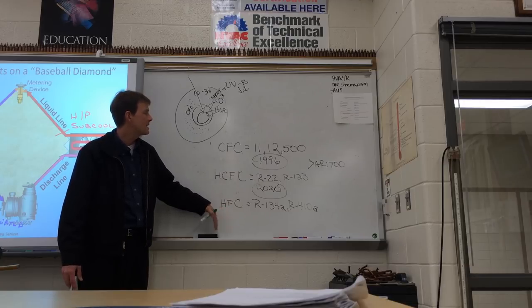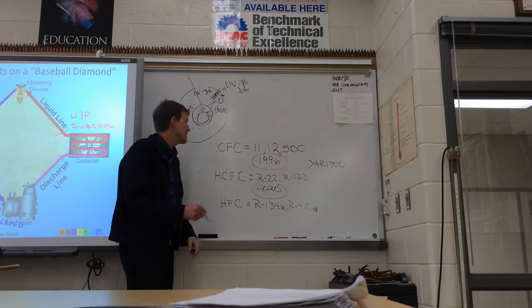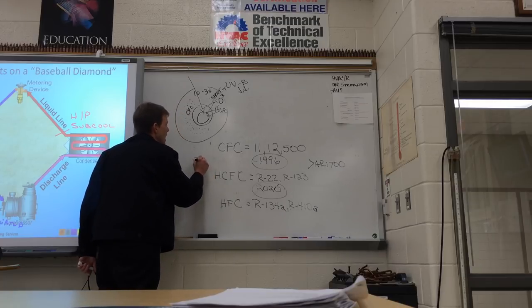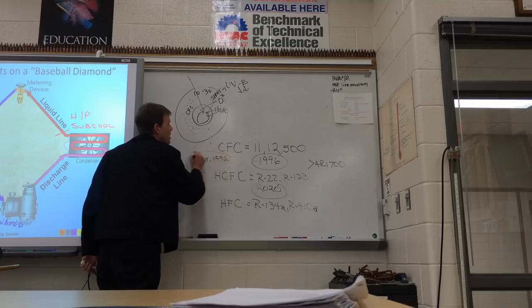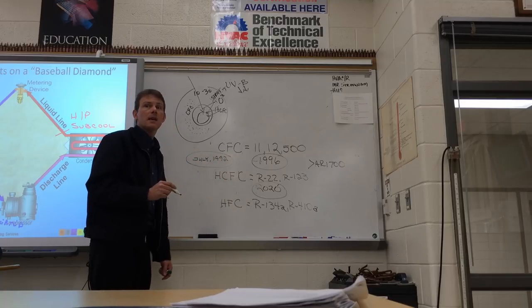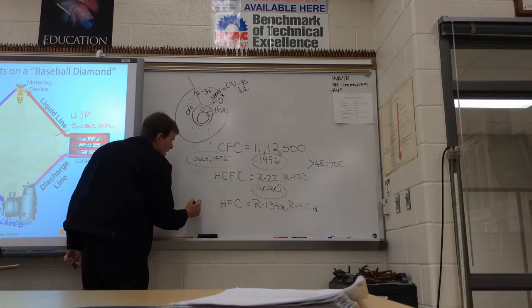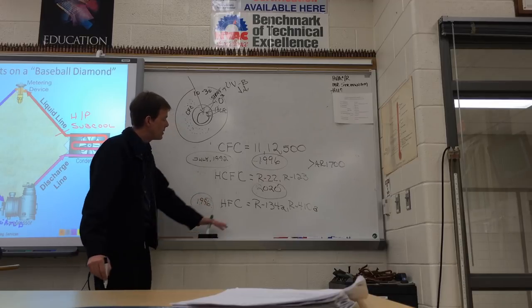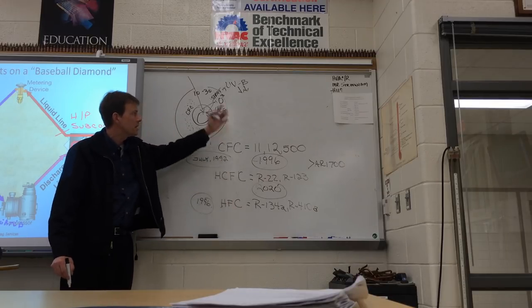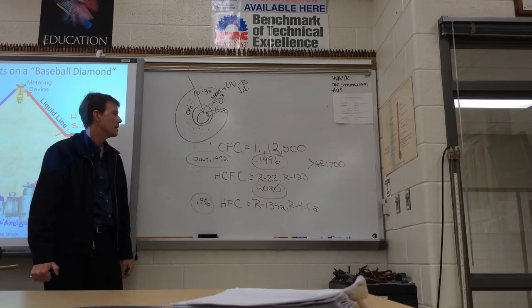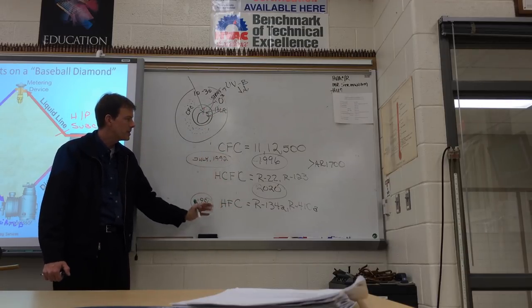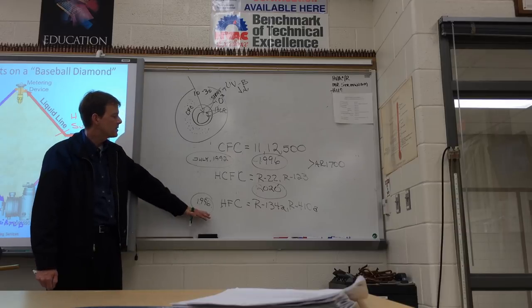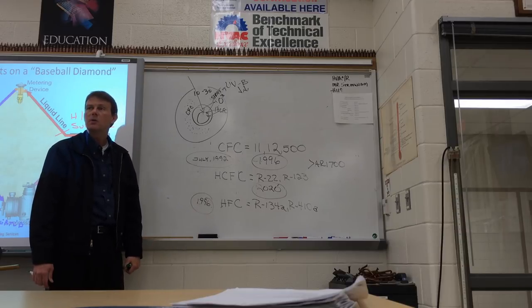So we couldn't vent these after July 1992. July of 1992, we had to start recovering all these refrigerants. And then these, after 1996, we couldn't vent them anymore. So we had to start recovering these refrigerants. Even though they didn't cause any ozone depletion, they still figured out that it was global warming. And ultimately, they're going to go to another refrigerant. It's not going to be these. These are just also going to be interim refrigerants.